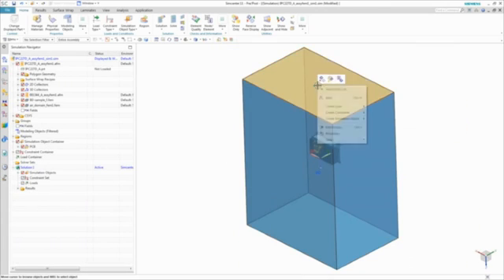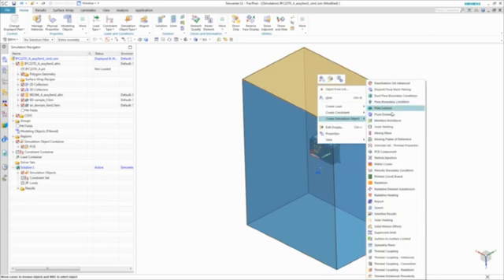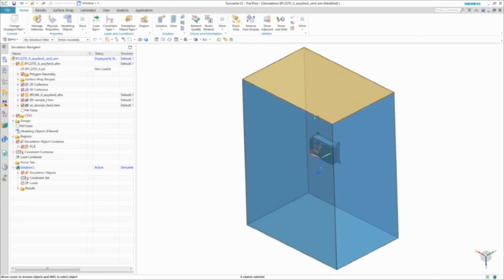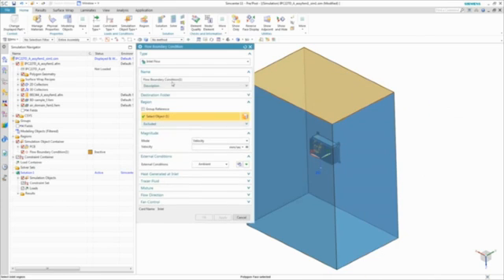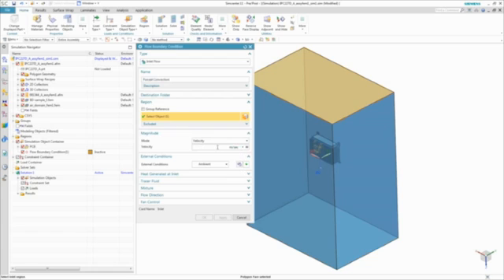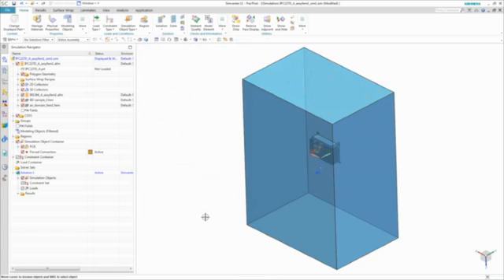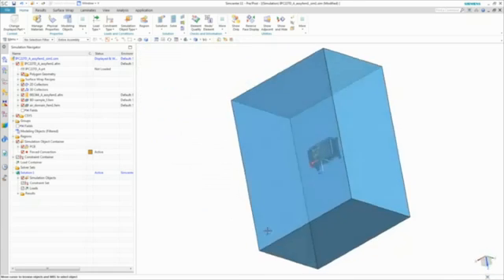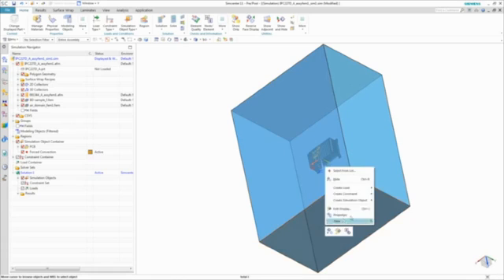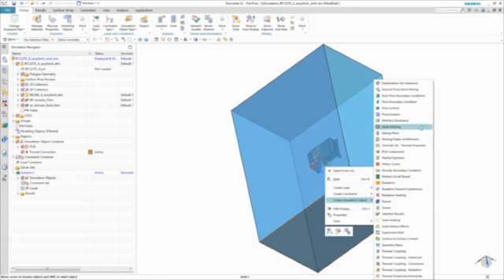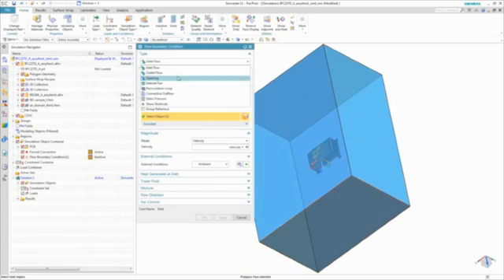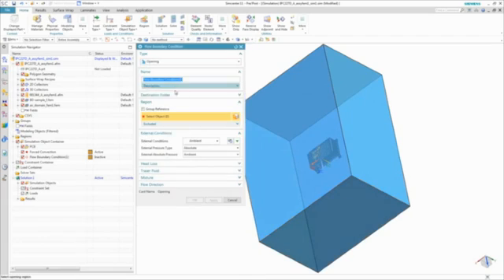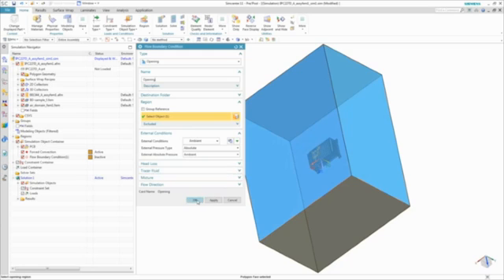To complete this model, flow boundary conditions are applied at an inlet to represent forced air flow of 5 meters per second from the ceiling onto the PC, which would be rack mounted. The flow outlet would be on the floor, which is typical of a data center setup. It's then necessary to create a thermal coupling between the external air domain and the casing to ensure we properly model the heat dissipation from the PC.